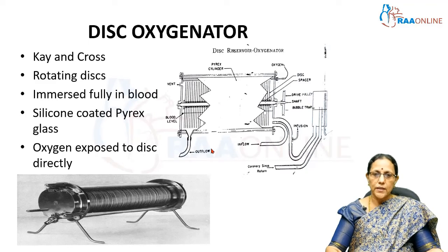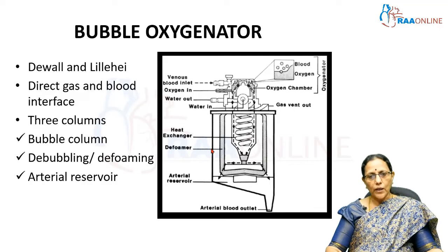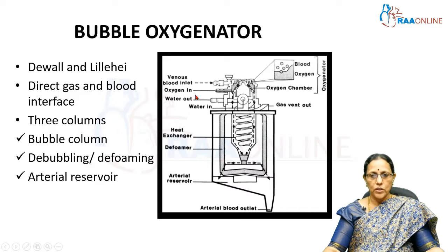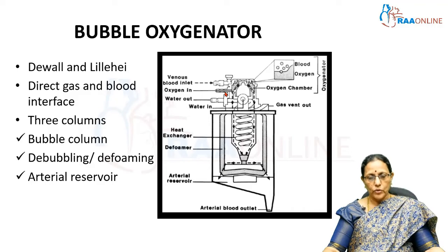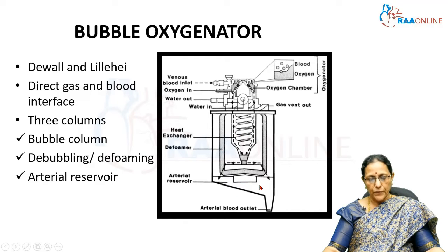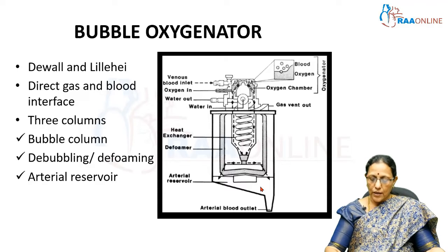Due to disadvantages like foaming, frothing, and trauma to the blood, the next generation of oxygenators evolved — the bubble oxygenator. The bubble oxygenator was designed by Dewall and Lillehei. Here there is direct interface of gas and blood, so whenever the venous blood drains into the oxygenator it is bubbled directly with oxygen. This bubbling may cause froth and foam, so these are collected in an arterial chamber which incorporates a de-foaming agent and a de-bubbling column. The foamed blood gets de-foamed and filtered, collected in the arterial reservoir, and is then taken by the arterial pump into the patient.